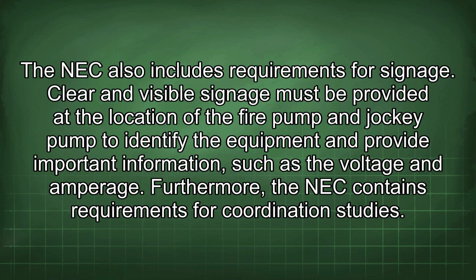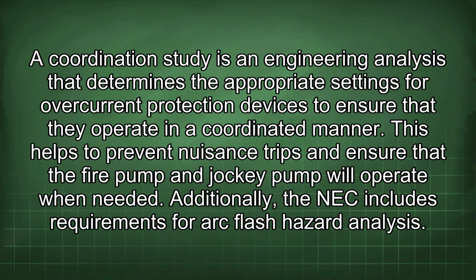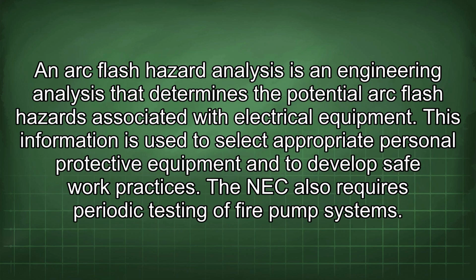Furthermore, the NEC contains requirements for coordination studies. A coordination study is an engineering analysis that determines the appropriate settings for overcurrent protection devices to ensure that they operate in a coordinated manner. This helps to prevent nuisance trips and ensure that the fire pump and jockey pump will operate when needed. Additionally, the NEC includes requirements for arc flash hazard analysis. An arc flash hazard analysis is an engineering analysis that determines the potential arc flash hazards associated with electrical equipment. This information is used to select appropriate personal protective equipment and to develop safe work practices.